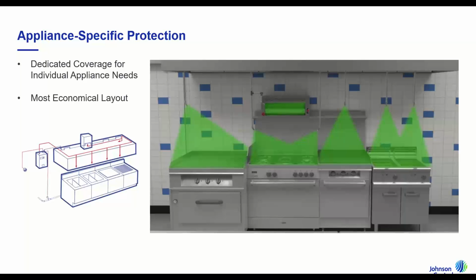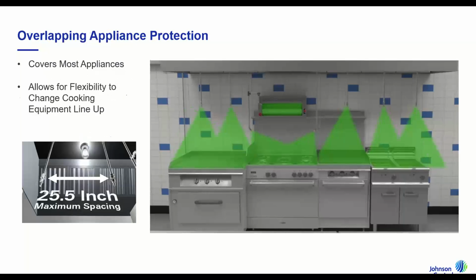So when we think about those three different product offerings, we do also have coverage offerings. When we look at appliance specific, this is essentially where you have dedicated nozzle coverage and agent application per appliance type. So a griddle, a fryer, a range, a wok, all of those would have different appliance coverages, which equates to different nozzle locations, different nozzle types, and then different flow characteristics of those nozzles. This is the most economical layout, as it's using only agent where it's needed. However, any changes to the appliance lineup would require fire suppression changes.